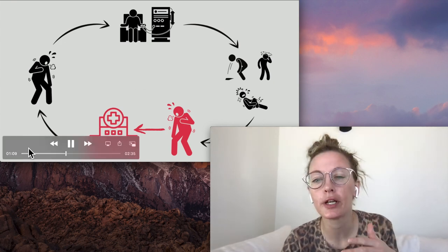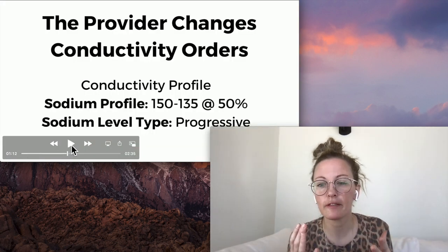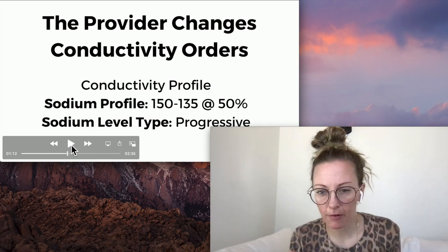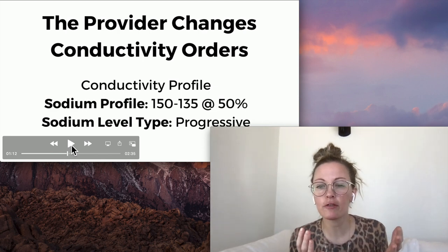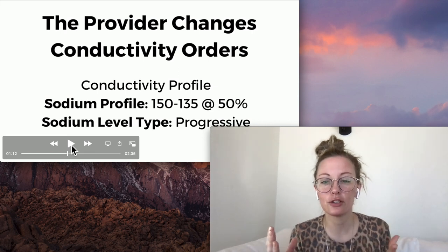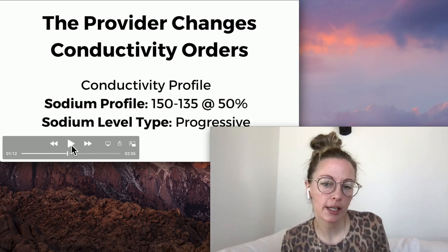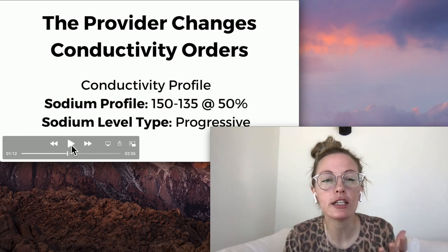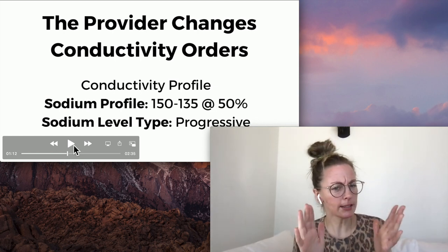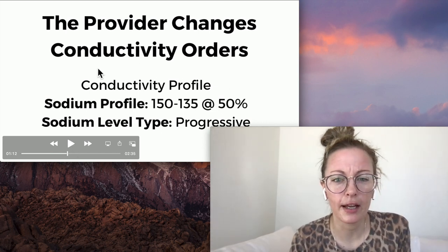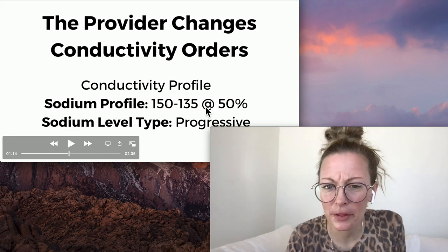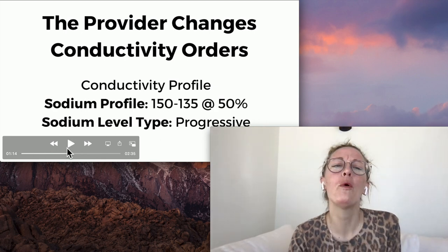Whatever we're doing isn't working and we need to try other things. Sometimes facilities do longer or extra treatments, but for some patients the answer is conductivity profiles. You talk to your provider: the patient has been hospitalized twice in the last 60 days, won't come in for an extra treatment — and the provider says let's try a conductivity profile. The order in your EMR might look like: 150 to 135 at 50% progressive. What does that mean?